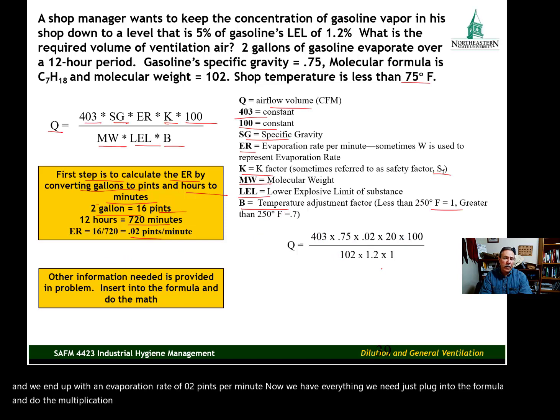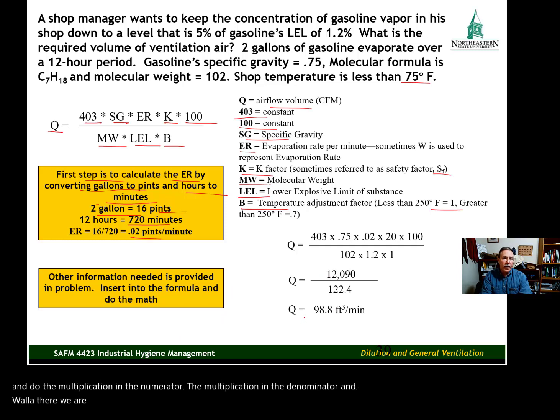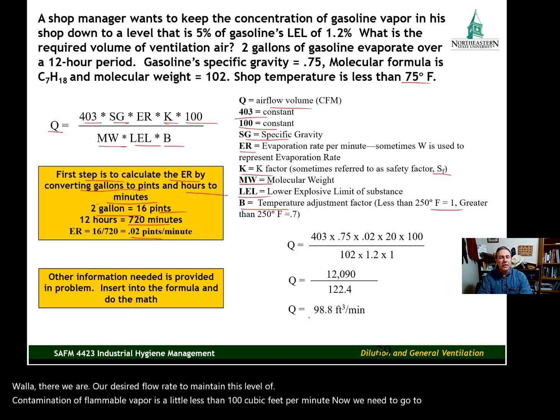Now we have everything we need to plug into the formula and do the multiplication in the numerator and the denominator. And voila, there we are. Our desired flow rate to maintain this level of contamination of flammable vapor is a little less than 100 cubic feet per minute. Now we need to go to our ventilation system and make sure it's providing that flow rate.